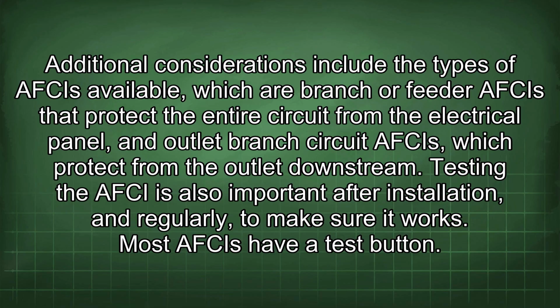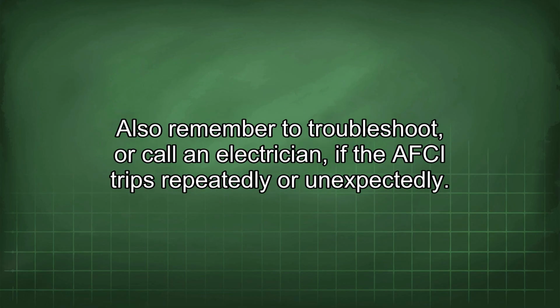Additional considerations include the types of AFCIs available, which are branch or feeder AFCIs that protect the entire circuit from the electrical panel, and outlet branch circuit AFCIs, which protect from the outlet downstream. Testing the AFCI is also important after installation and regularly to make sure it works. Most AFCIs have a test button. Also remember to troubleshoot or call an electrician if the AFCI trips repeatedly or unexpectedly.